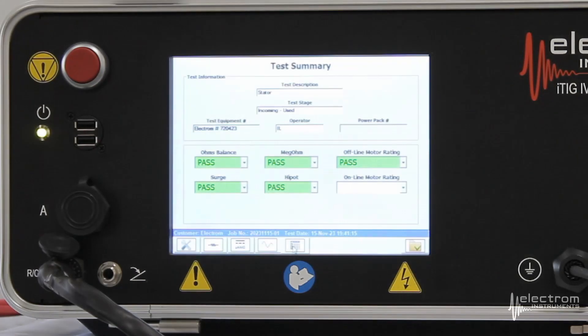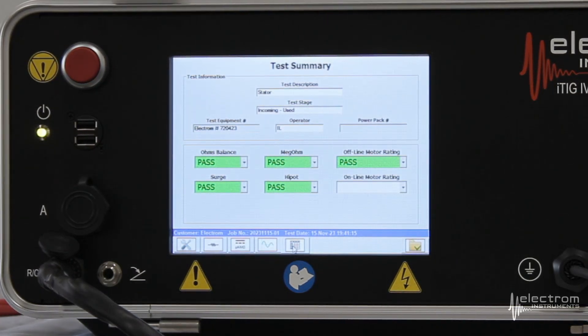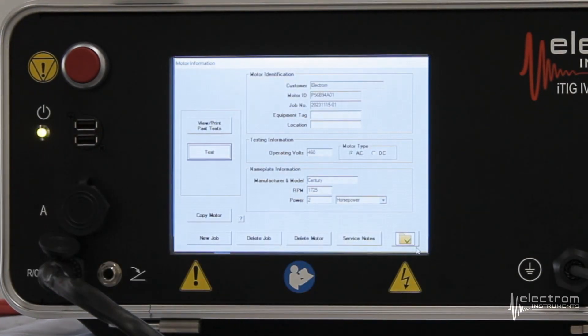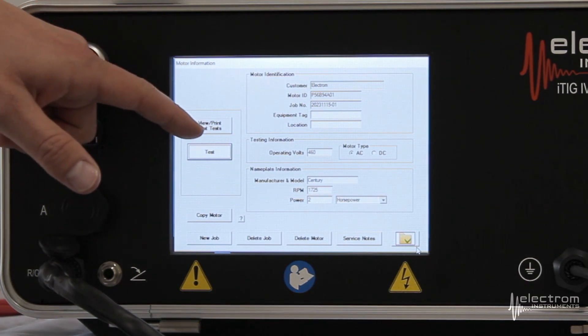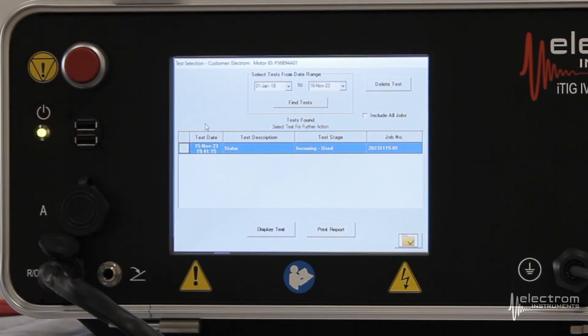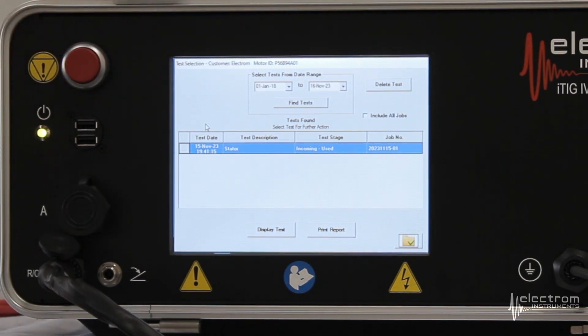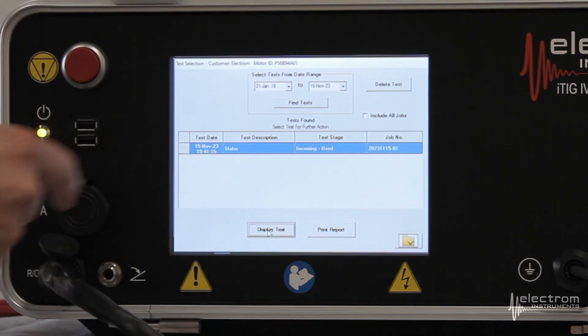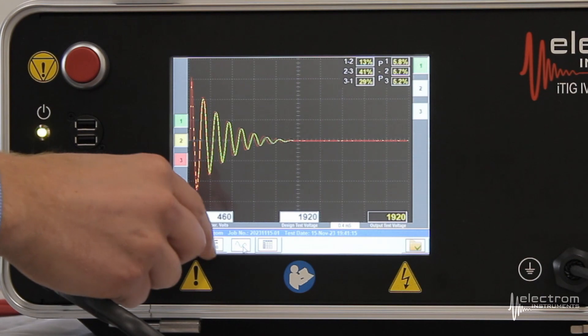On the last tab — the test summary — this motor tested fine. All pass. We're done with the test set. Hit the folder button and everything is automatically stored; there is no manual save operation. We can click View Print Past Test and we now see the time and date stamp, including the test description, test stage, and job number. It's very useful to include these three pieces of information for reporting and for tracking where you were in the test process. You can also select Display Tests to go back and review the exact same screens we were just on.